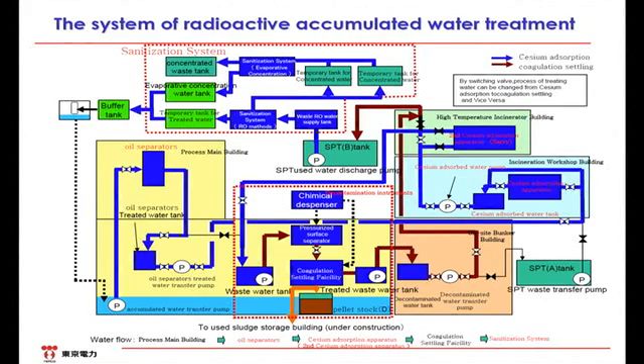This is the overall system chart. After the water is stored in the first and second basement of the process main building following the dotted line, it goes into the oil separators and next into various processes such as the cesium adsorption apparatus, decontamination instruments, and then the second cesium adsorption apparatus. The processed water is temporarily stored in the tank called SPTB. Currently, ALPS, which is a decontamination instrument, is standing by as a backup to reduce waste sludge generated. Currently, the water is processed by Kurion, which is a cesium adsorption apparatus, and SARRY, which is the second cesium adsorption apparatus.